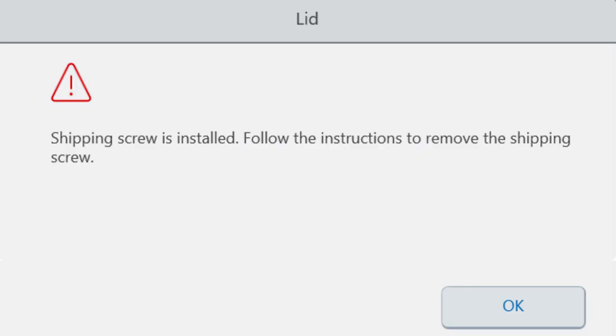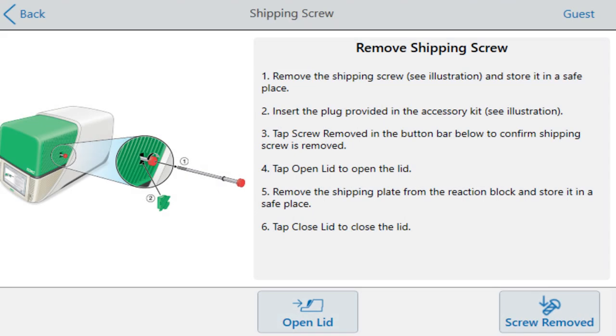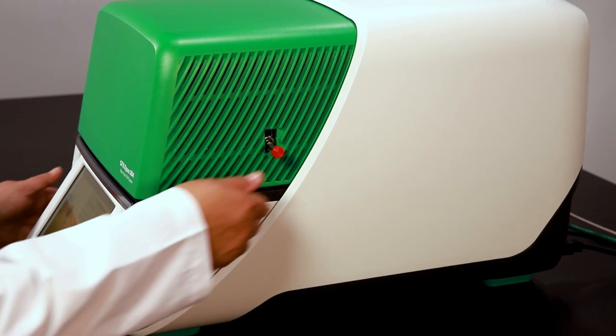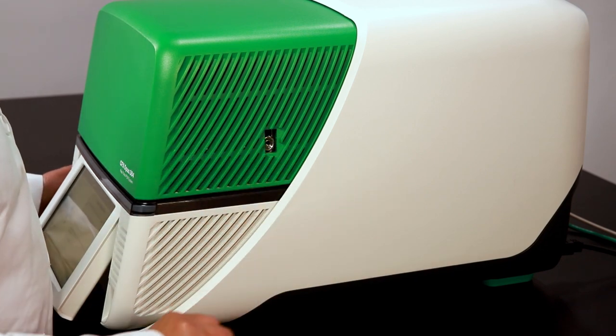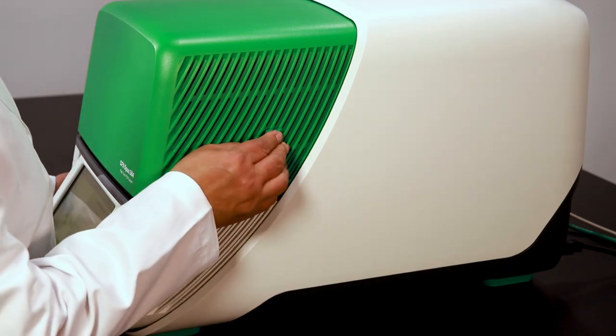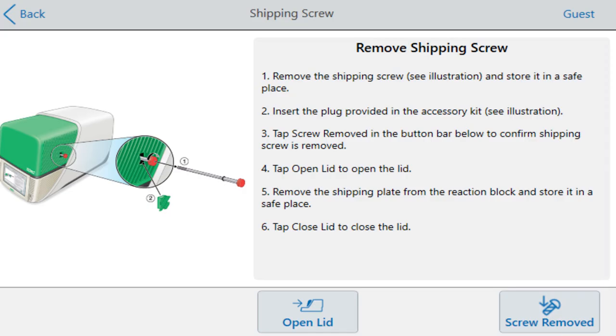The screen will display a warning about the installed shipping screw. Press OK to view instructions for removing the shipping screw. Remove the shipping screw by turning counterclockwise until the screw can be pulled out. Use the shipping plug to cover the hole where the shipping screw was. Press Screw Removed on the touch screen to confirm that you have removed the shipping screw.